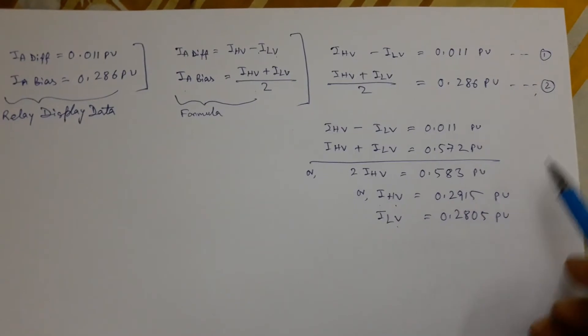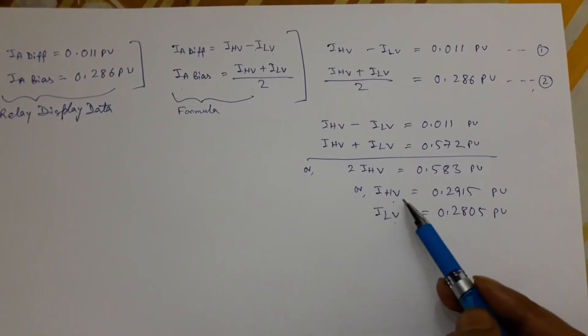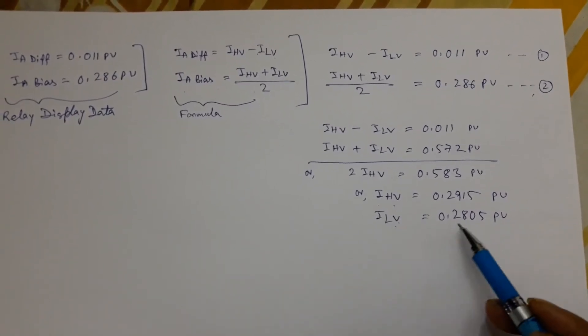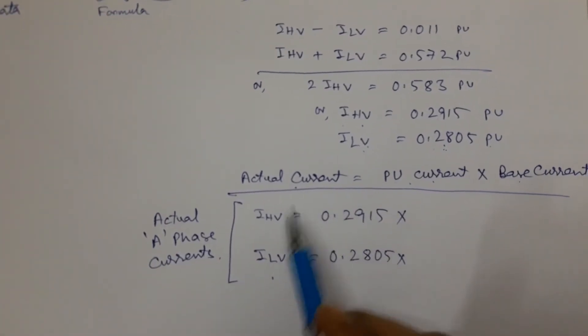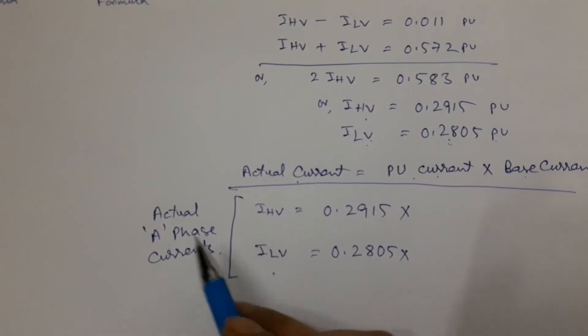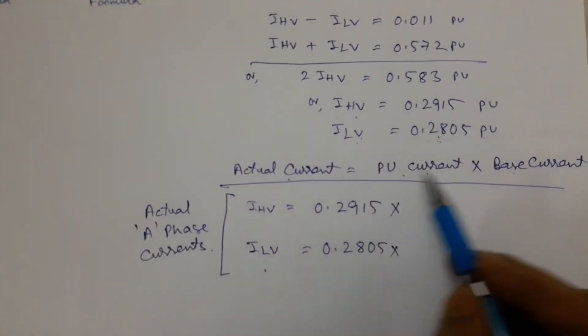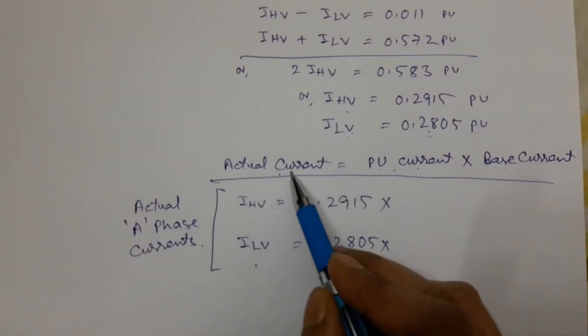By using these two formulas, we can easily find value of HV and LV side currents in per unit. Now we can calculate actual value of HV and LV side currents of A phase by using this formula. Actual current can be obtained by multiplying per unit current with base current.